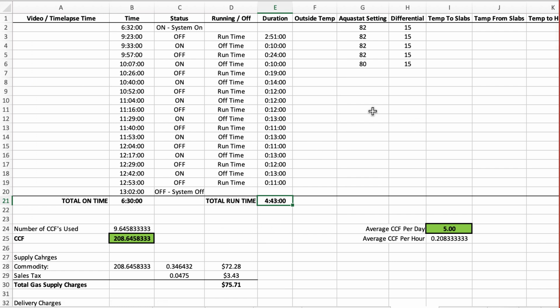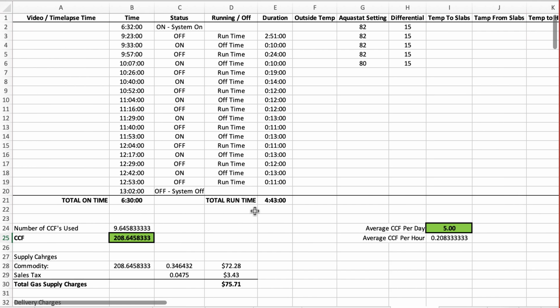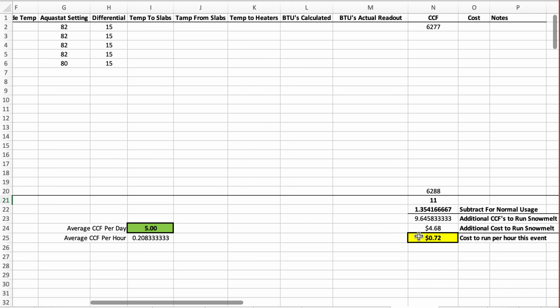Here's the seventh. I don't remember the title of this video. I'll put all these up above in the YouTube cards if you want to click on all these as you go through this. But this looks like a short 1 day event. The snowmelt system was on for 6.5 hours. It ran for 4 hours and 43 minutes. I used 11 CCFs of gas. Subtracted out 1.4 for normal use. That means 9.6 was used just for the snowmelt. It cost me about $4.68 to run, 72 cents an hour. Again, because it was so short, that hourly rate is a little higher.